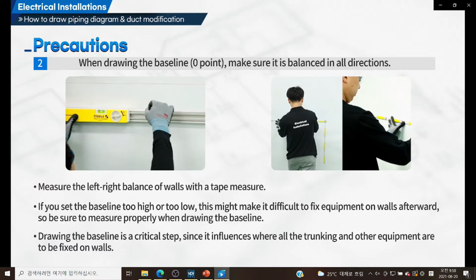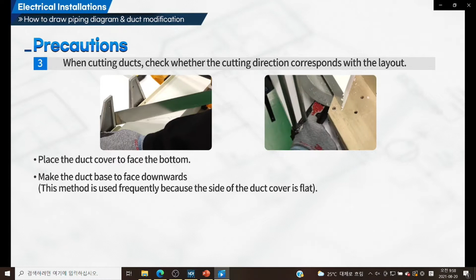Place the duct cover to face the bottom, and make the duct base face downwards. This method is used frequently because the side of the duct cover is flat. When cutting ducts with the hand miter saw, there are many cases of misjudging the cutting direction, so pay extra attention to it. After cutting ducts with the hand miter saw, there will be 2 cut sections for each duct. These sections should be marked with numbers since they will all be used afterward.